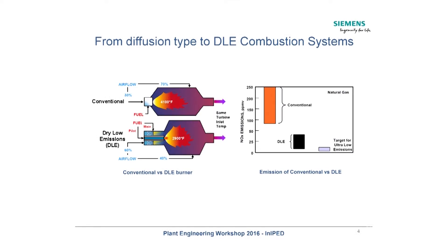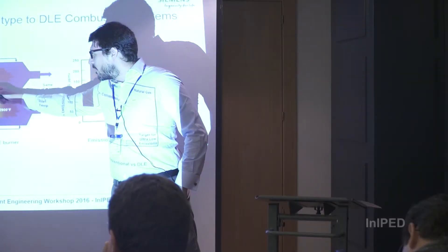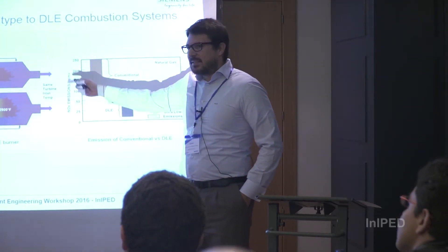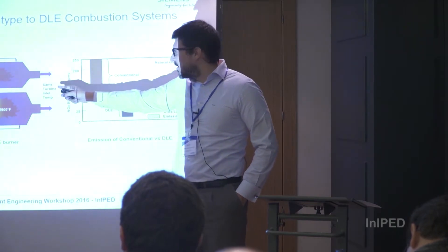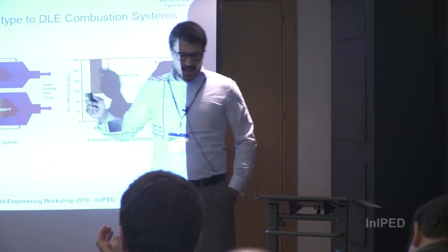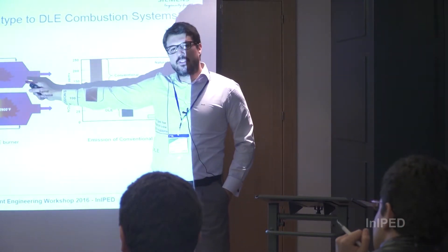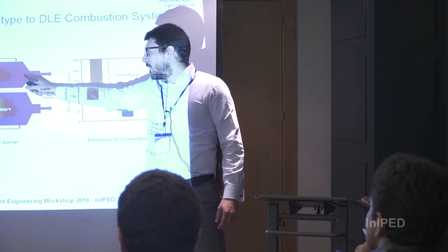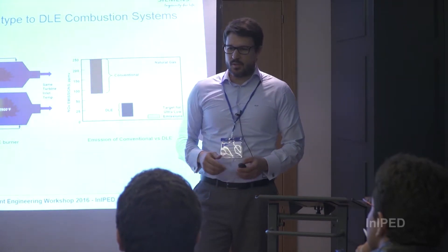We have here an example of a conventional burner versus a dry low emissions burner. The main difference is that in the conventional burner, air and fuel enter together without previous mixing in order to create a flame that is very hot at the beginning. The tactic to reach a decent turbine inlet temperature is adding cooling media — normally air — at this stage. However, adding only air will not reduce NOx emissions, so the traditional way to abate emissions has been to use a diluent added at this stage of the combustor.